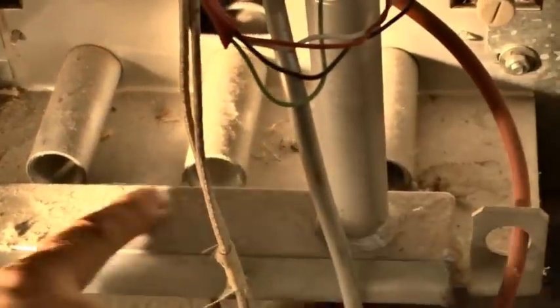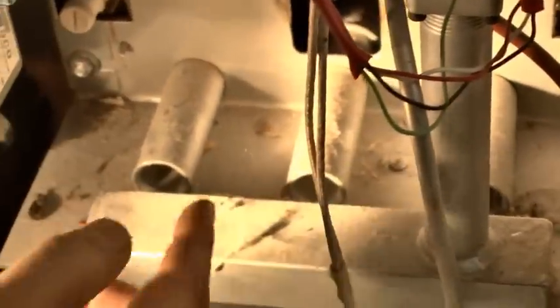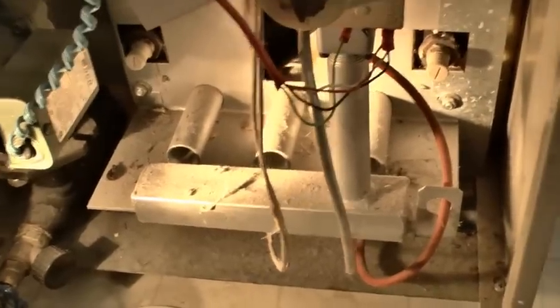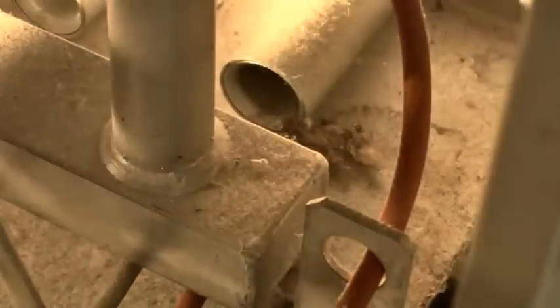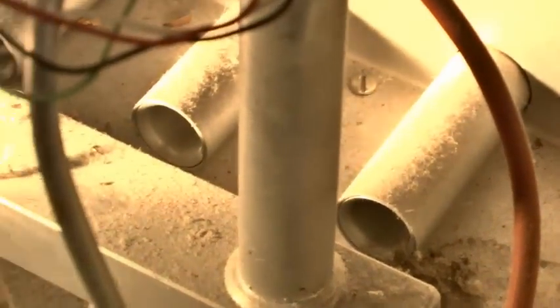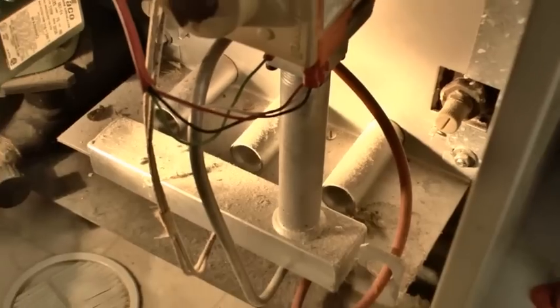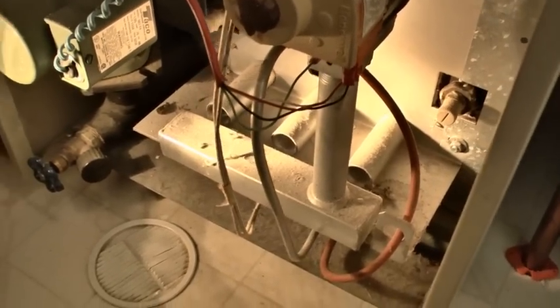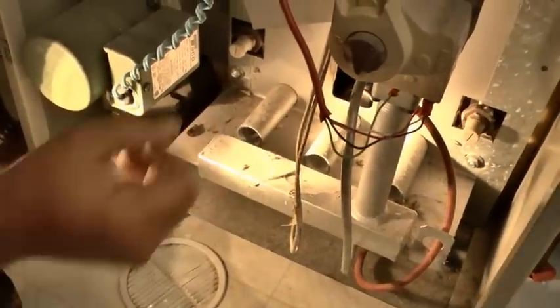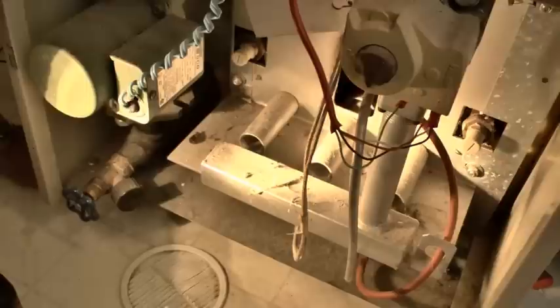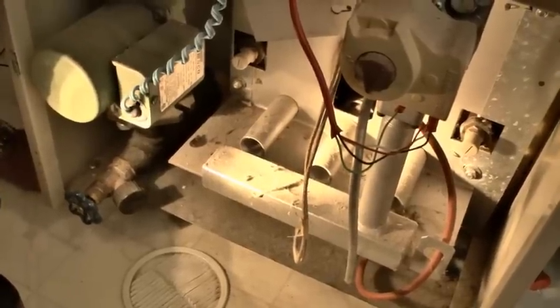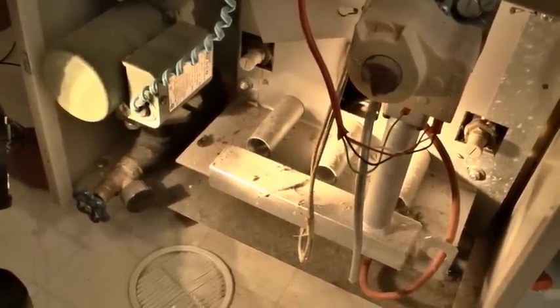The primary air mixes with the gas that's coming out of these orifices, and you can see all this dirt, this lint, because it's in a laundry room. Here's a bunch. It's critical that it doesn't go in with the burners, with the gas into the burners. Those little red things that we were seeing on the burn, there's a really good possibility it's little pieces of this that are going through there, and then they heat up, and that's that little red coloring that you see way on the tips of the flames periodically.